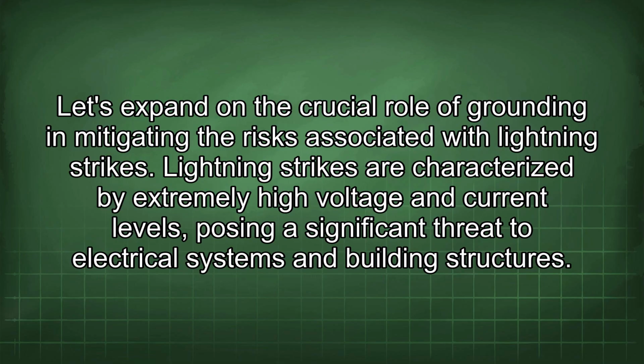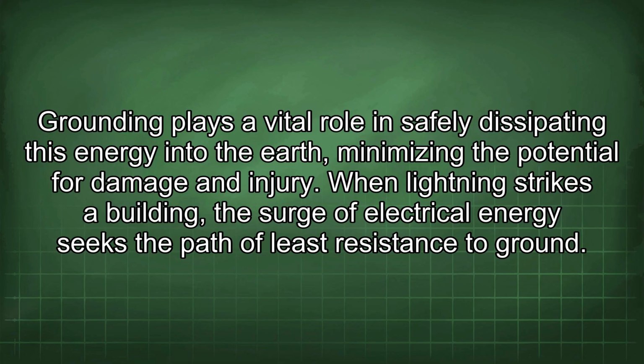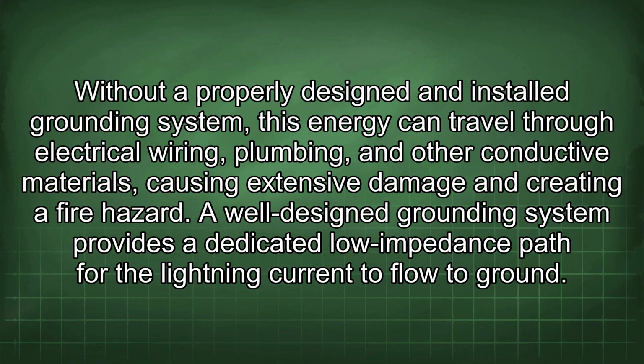Let's expand on the crucial role of grounding in mitigating the risks associated with lightning strikes. Lightning strikes are characterized by extremely high voltage and current levels, posing a significant threat to electrical systems and building structures. Grounding plays a vital role in safely dissipating this energy into the earth, minimizing the potential for damage and injury. When lightning strikes a building, the surge of electrical energy seeks the path of least resistance to ground. Without a properly designed and installed grounding system, this energy can travel through electrical wiring, plumbing, and other conductive materials, causing extensive damage and creating a fire hazard.